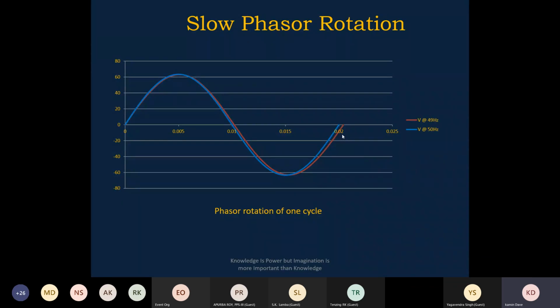So for the phasor plotting, the data values have to be tracked based on the 50 hertz component rather than the 49. The window has to be aligned again with the 50 hertz component. Otherwise, the understanding and analysis of the fault quantity will be wrong. This is how you look at it here: the 1 cycle window for 50 hertz and the 1 cycle window for 49 hertz.